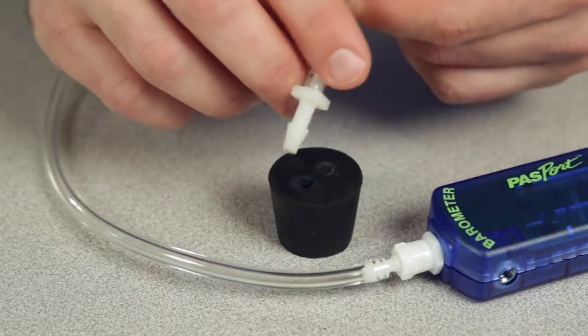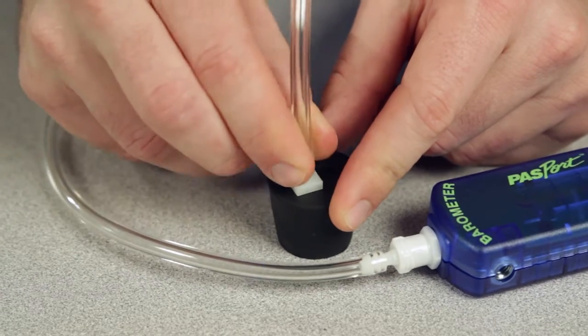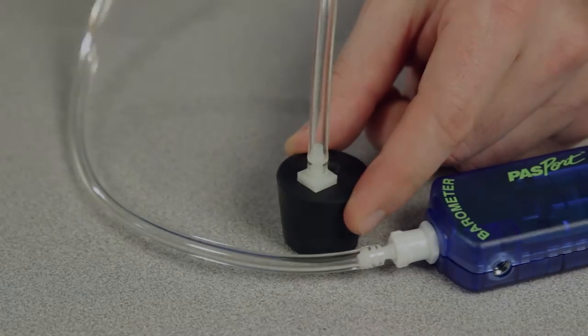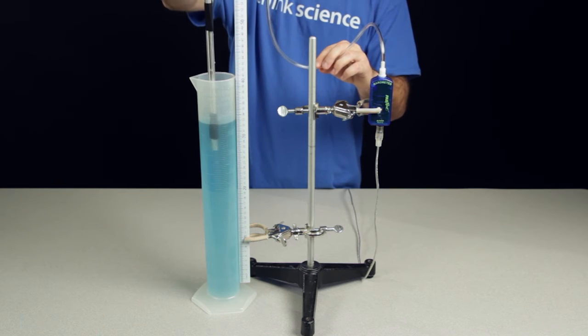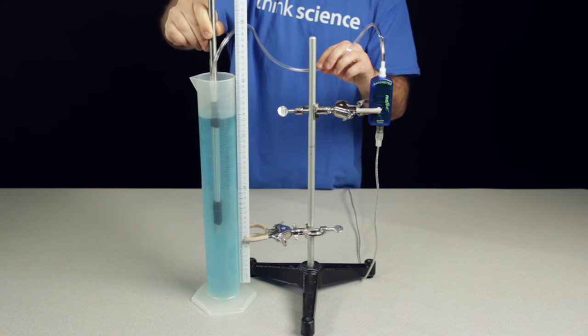Connect the open end of the tubing to accessories using the inline connectors or other tubing connectors, or keep the end of the tubing open and use the tubing as a basic probe to measure pressure at the position of the tubing's open end.